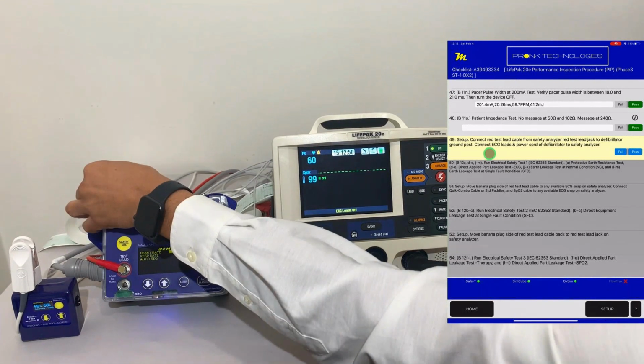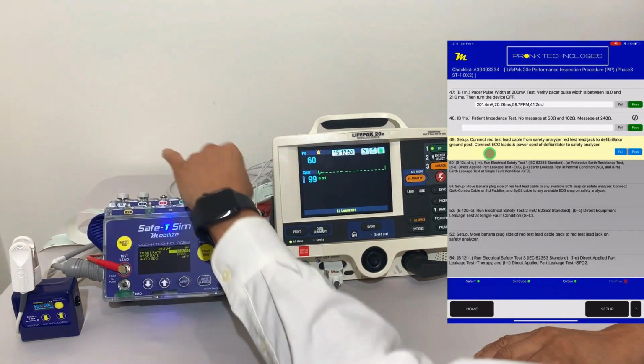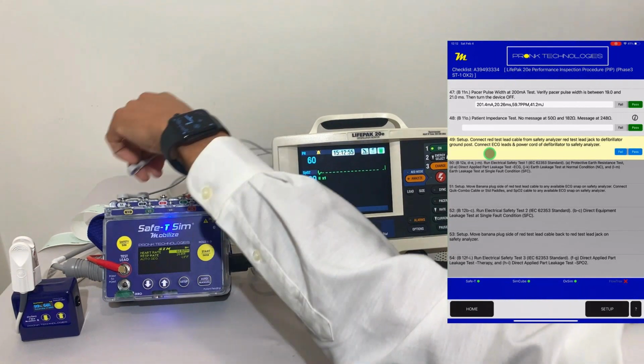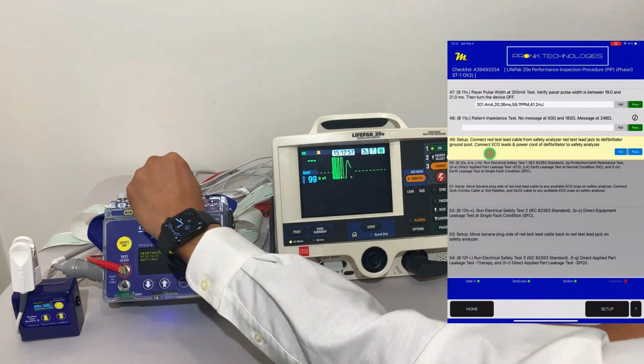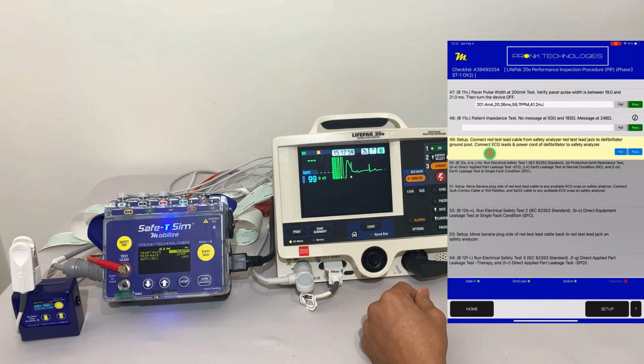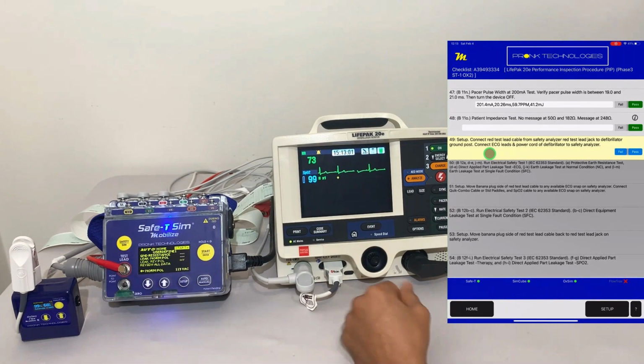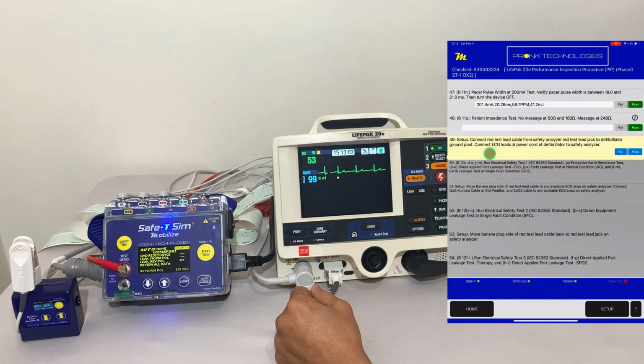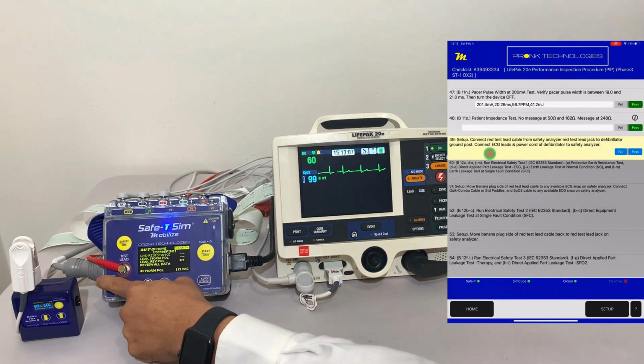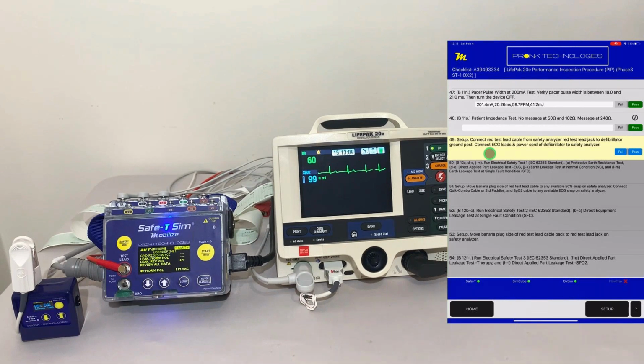We're going to verify that the results are within the proper specification. So bear with me just a moment here. Got it connected. We want to get ready to do an electrical safety test. We'll go into the safety test mode to get ready to do that. We've connected the power cord to the safety analyzer, and we've set up this test according to this procedure here so we can get started.